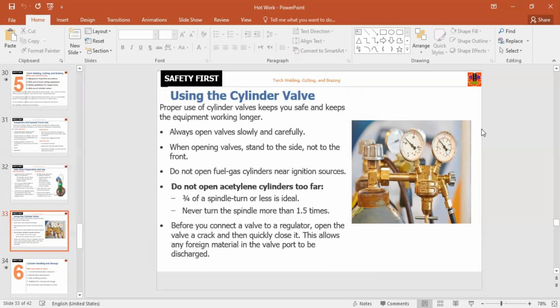Three-fourths of a spindle turn or less is ideal. Never turn the spindle more than 1.5 times. Before you connect a valve to a regulator, open the valve a crack and then quickly close it. This allows any foreign material in the valve port to be discharged.